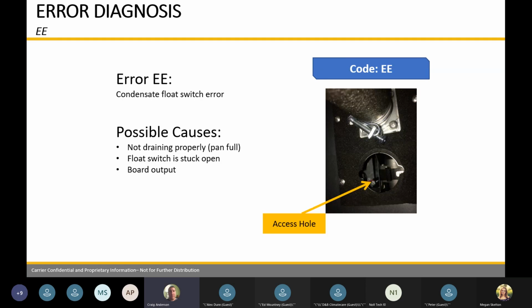So here's an EE float error. Like I was telling you on that ducted unit, they were all upside down. It went right into an EE code, all of them, because the float was upside down. So on those ducted units, there's an access hole to get in there and look at that float to see if it's stuck, if it's overflowed or anything like that.